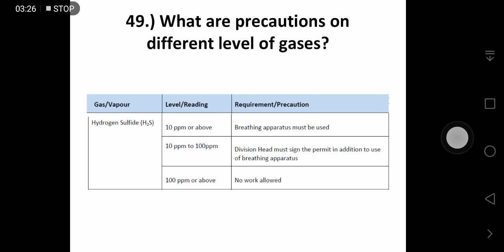Less than 20% breathing apparatus must be used and division head must sign the permit, and above 23.5% no work is allowed. For hydrogen sulfide, for 10 ppm or above, breathing apparatus must be used. For 10 ppm to 100 ppm, division head must sign the permit in addition to use of breathing apparatus, and above 100 ppm, no work is allowed.